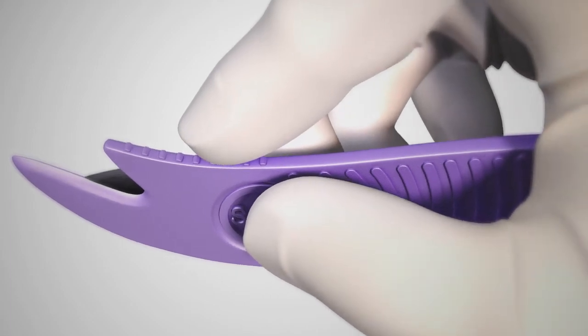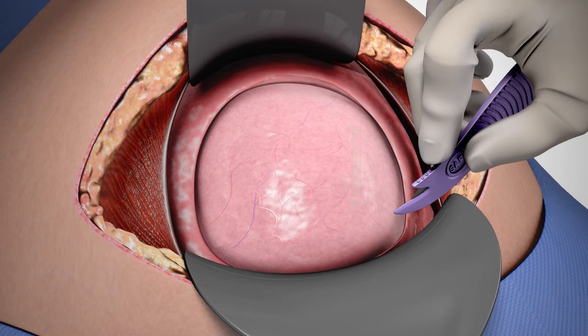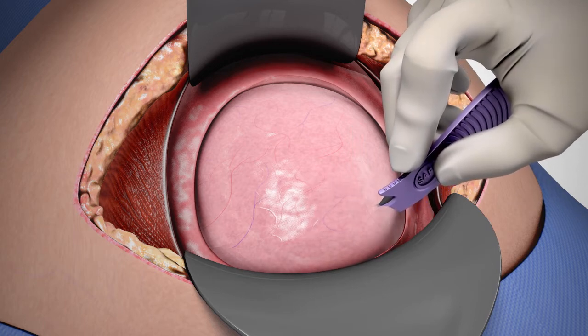The goal is safe entry. See Safe allows the surgeon to enter the uterus safely without the need for a traditional scalpel, regardless of uterine status. By applying slight downward pressure to the base of the handle while running the tip along the striations of the tissue, the tip will catch either in a striation or a forming ripple in the uterine wall.